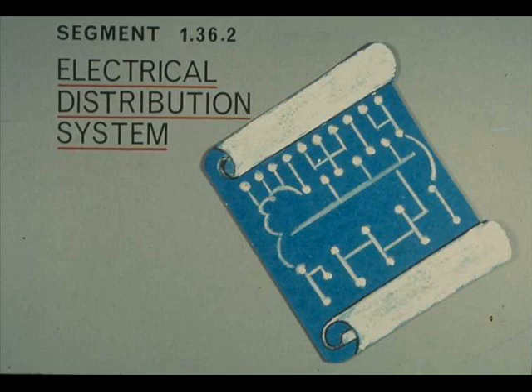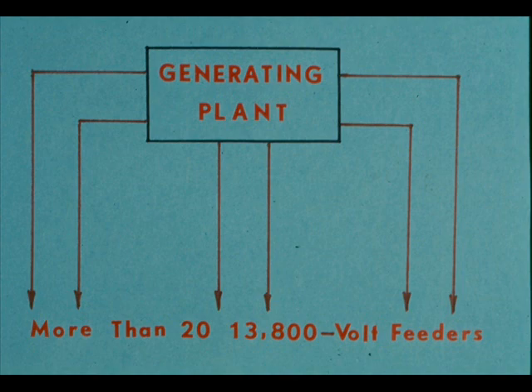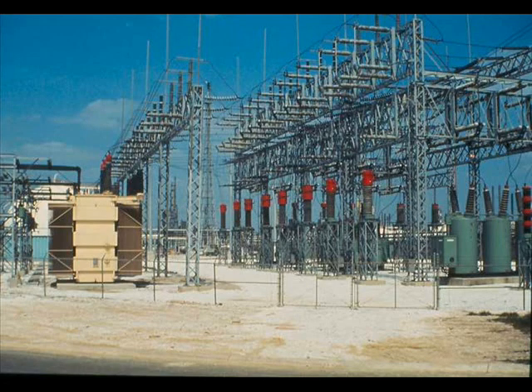For greatest efficiency in your operation of electrical equipment, you must know the electrical distribution system of your refinery or plant. Some industrial plants generate all or part of the electricity they use; others buy it from a utility company. In either case, there is at least one relatively high voltage feeder line from the generating plant or from a power transmission line. The number of feeders and the voltage they carry depend on your plant's needs. In one large refinery, more than 20 feeders carry 13,800 volts to various parts of the plant. One of these 13.8 kV feeders supplies electricity to the 14,400 horsepower driver of the refinery's largest compressor.